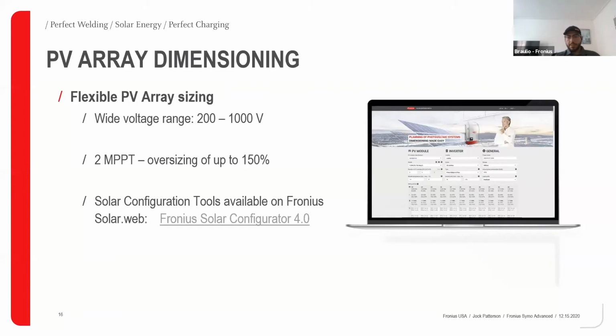PV array dimensioning is pretty flexible and easy. Our inverters offer a wide voltage range that goes from 200 to 1,000 volts with 2 MPP trackers, allowing for oversizing of up to 150%. If you're relatively new to string inverters, we have a string configuration tool that makes it very, very easy to design with our inverters. A new feature that I learned about is that even as the module sizes are increasing every year, and let's say our software team is not able to upload the newest data sheets on the website, if you have your login, you're able to add the new module model, and it's going to be saved into your profile. So that way, the design is going to be a lot faster because everything is saved.